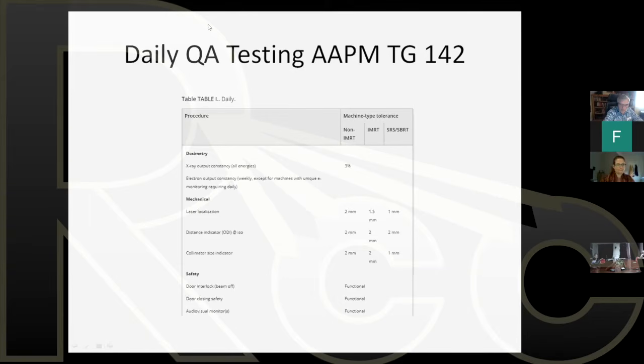Safety is very important, and in the US, if any of these do not work, you cannot treat the patient. So say, for example, that my therapists come in and they find that the door interlock is not working, that the beam does not shut off if the door is open. Well, in the United States, most states have said that if the door interlock doesn't work, you cannot treat the patient that day. Even though you can see the patient, even though you may have someone posted by the door to make sure nobody accidentally enters the room, many of the states, at least the states that I work in, say that you cannot treat the patient that day. The door interlock must be working in order for the machine to be safe to use.